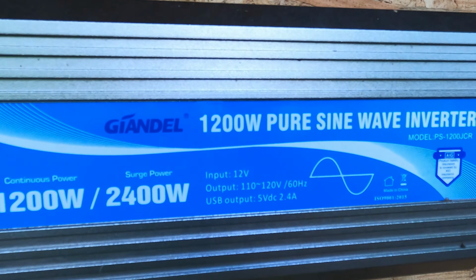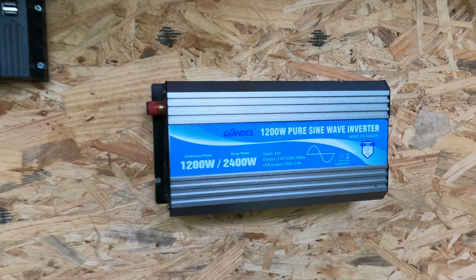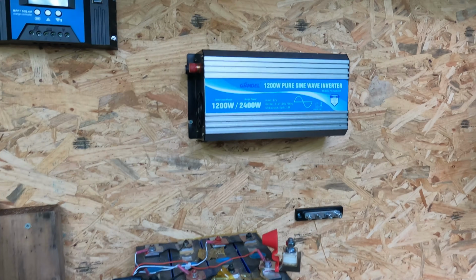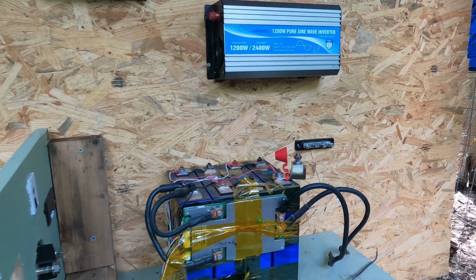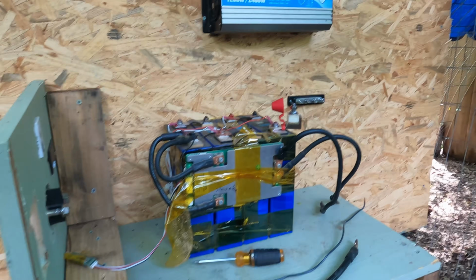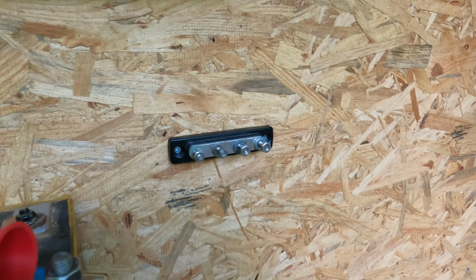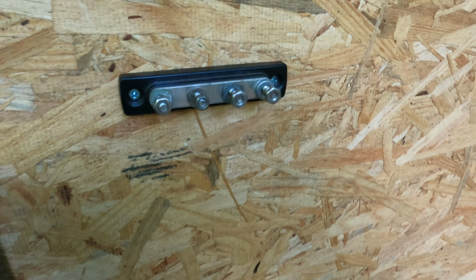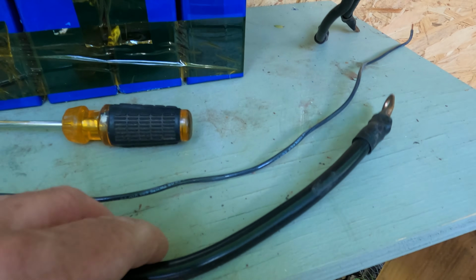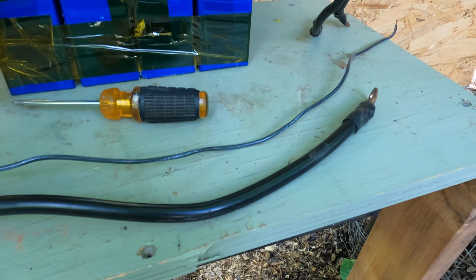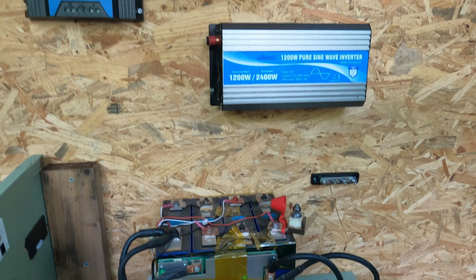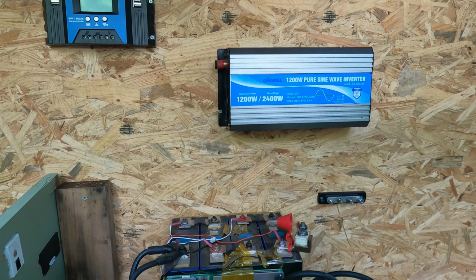Let's go back up to the inverter. It's 1200 watts, and this is a 12-volt system, meaning the maximum current that could run through is 100 amps. So I have to make sure my bus bars and wire are rated for that. This is a 100 amp bus bar, and this thick wire is 2 gauge, which can handle well over 100 amps. So even though I'll never actually run 100 amps through here, I want to build it like I will.